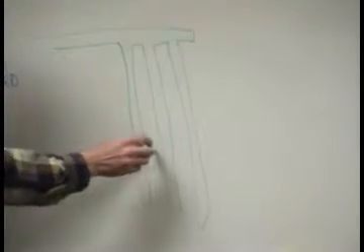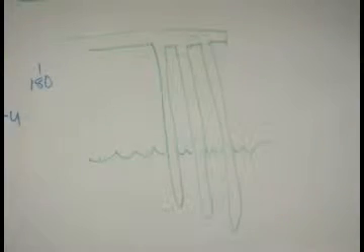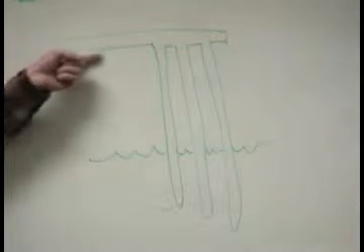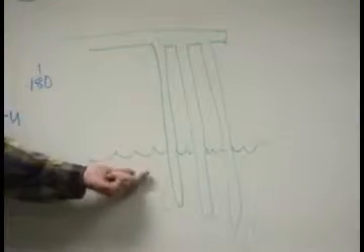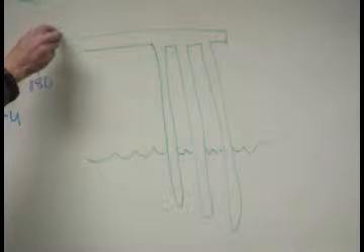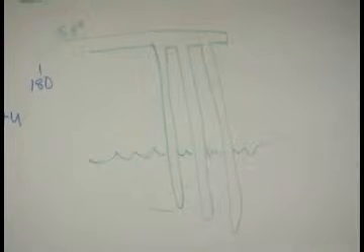Depending on where the water table is, there's often a lot of water down there, so it makes a pretty good heat sink. You're pumping hot or cold water out there, and it goes through that and comes back hopefully around 55 degrees. Say you're trying to heat with that. Heating with a 55-degree heat source is one whole lot better than trying to heat with a 30-degree or a 20-degree heat source. Your efficiency is really good if you can keep that temperature up into the 50s. So that's one obvious disadvantage there: you've got to drill some wells. That's fairly expensive to do.